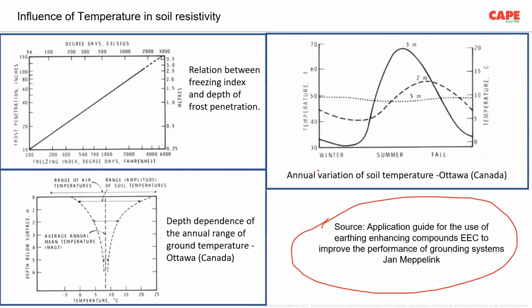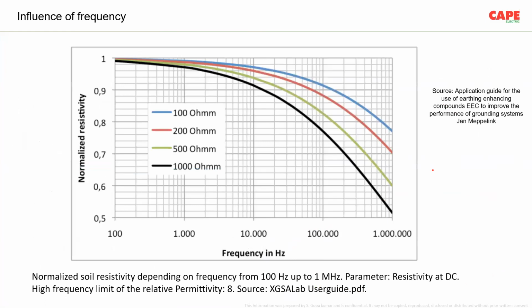What we are trying to find out from this paper is that in winter and in summer, there is a drastic change in the resistance or in the temperature. So basically, in countries where you have sub-0 degrees, for example minus 10 degree, minus 15 degree for longer durations, the soil is really dry. There is no moisture and the temperature is very low. Under that condition, the earth electrode becomes a little bit risky.